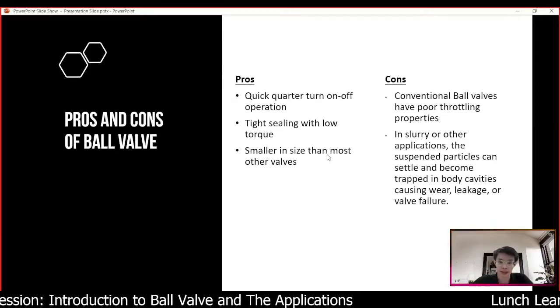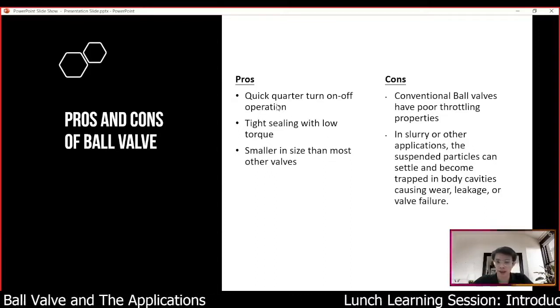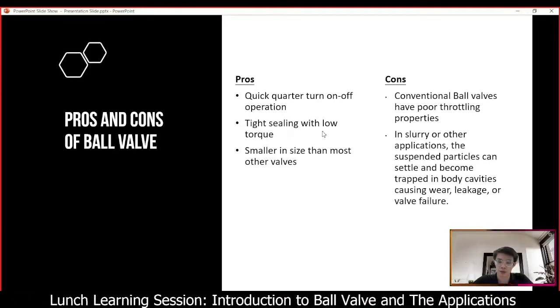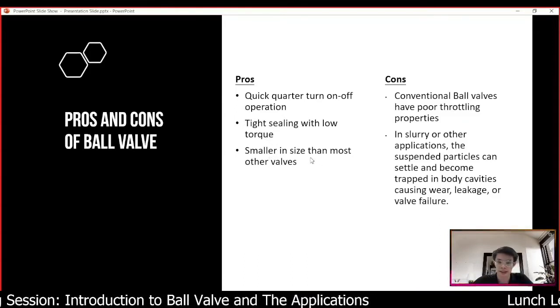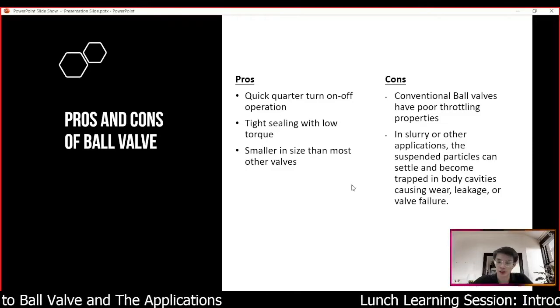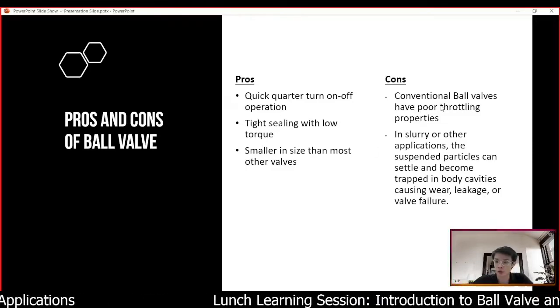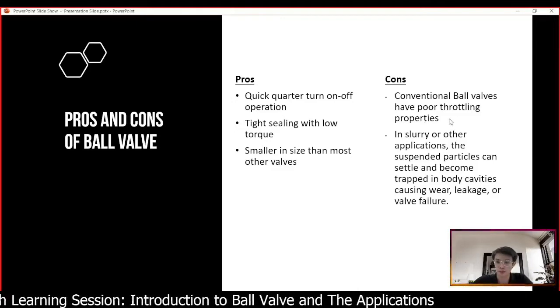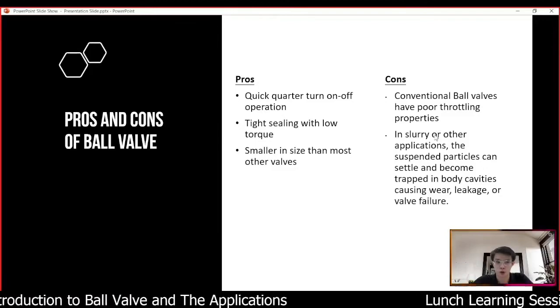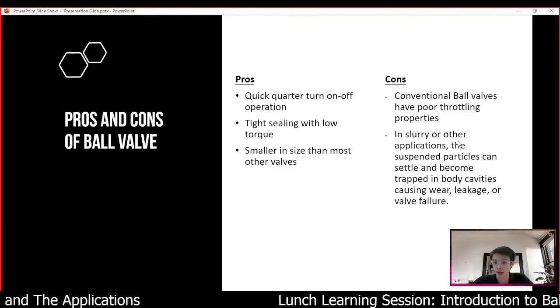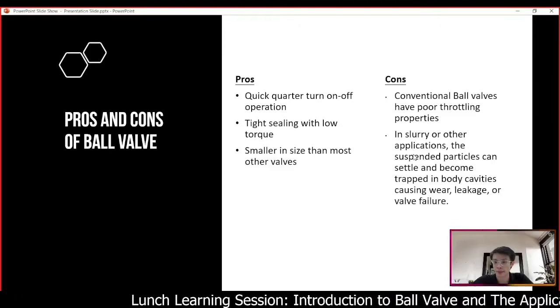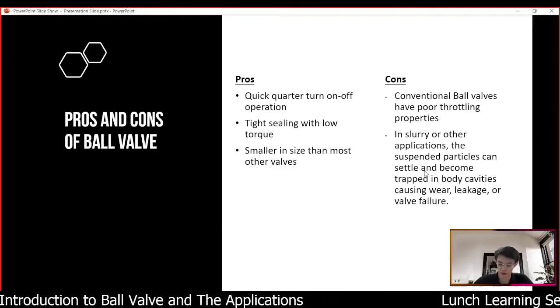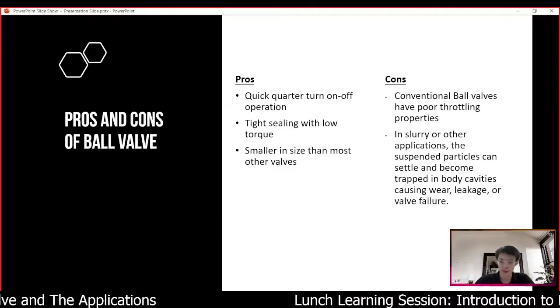For the pros and cons of ball valves: the pros are quick quarter-turn on/off operation, tight sealing with low torque, and smaller size compared to most other valves. The cons are that conventional ball valves have poor throttling properties and are not suitable for control valve applications. Also in slurry or similar applications, suspended particles can settle and become trapped in the body cavity, causing wear, leakage, or valve failure.